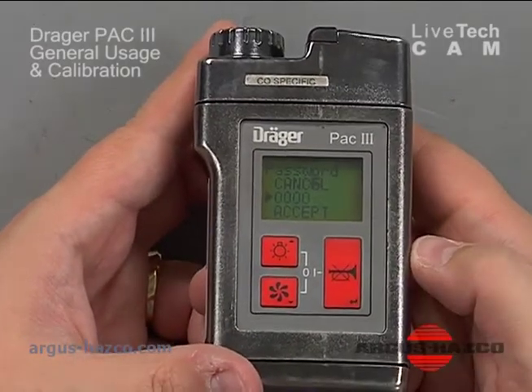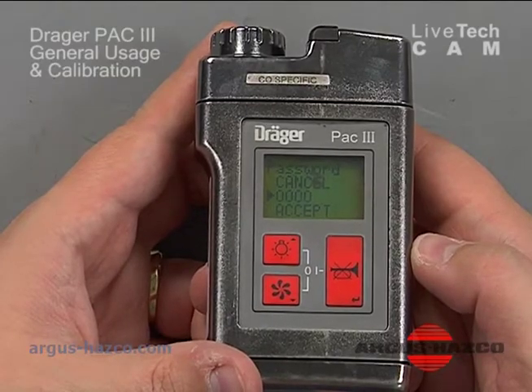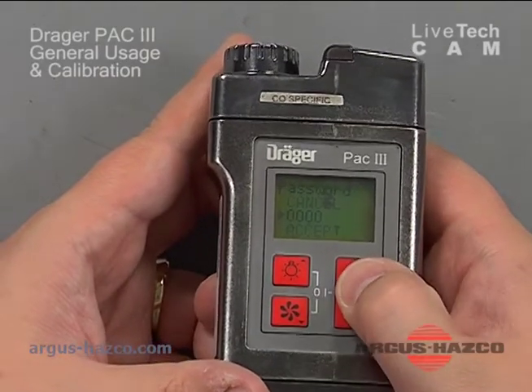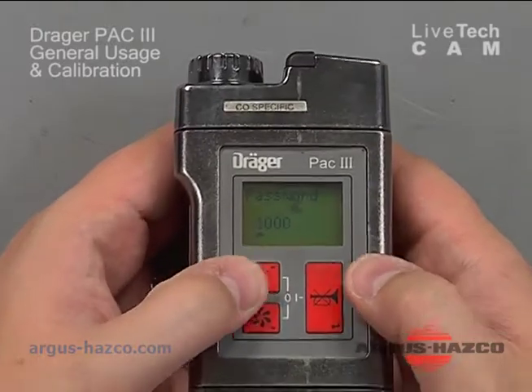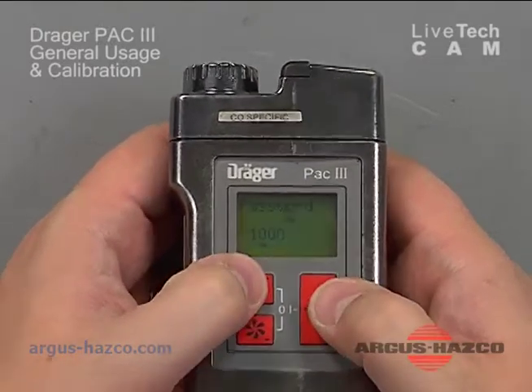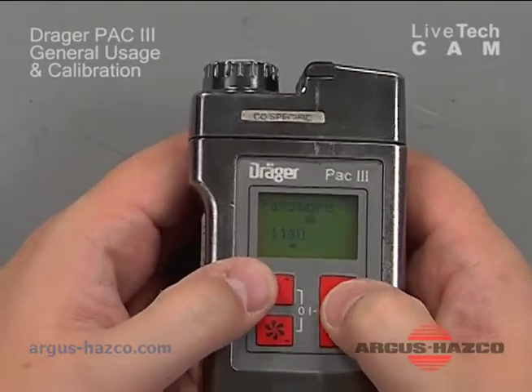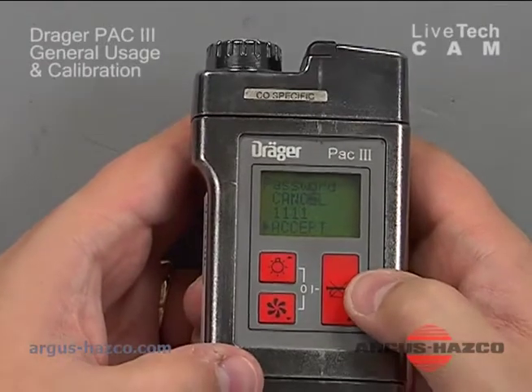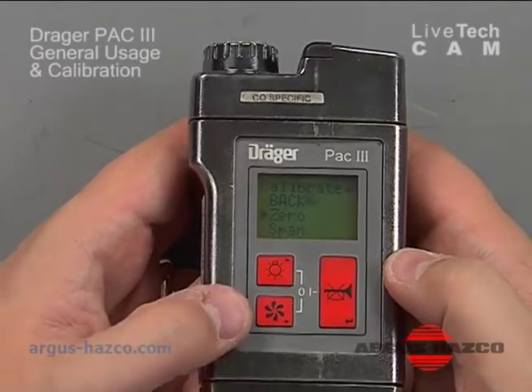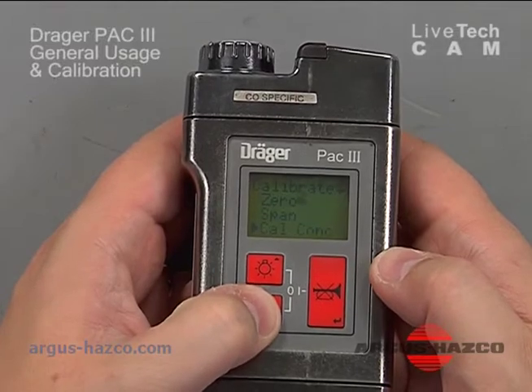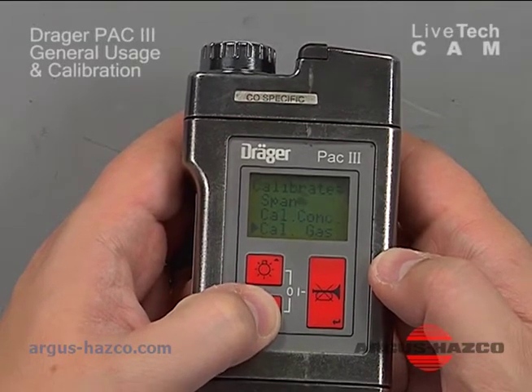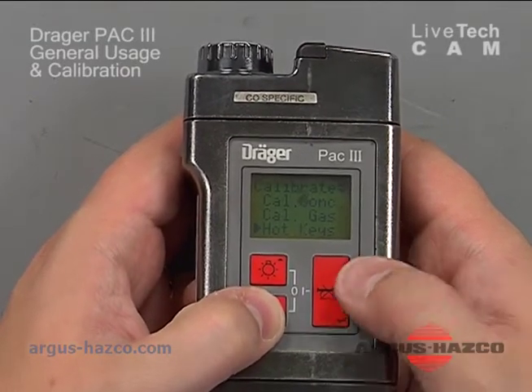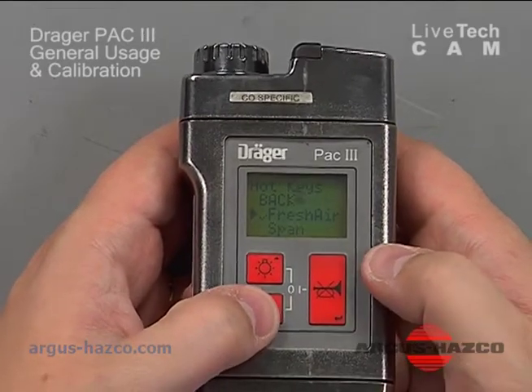And then it's going to ask you for a password. That's why your hotkey is important, because you can bypass all this. The password you need to enter is 1000. So you enter up to 1 and then accept it. Now you can zero, span, you can verify the cal concentration, your calibration gas you're using, and there's your hotkeys you can enable. To enable the hotkeys, you simply make sure that they're checked.